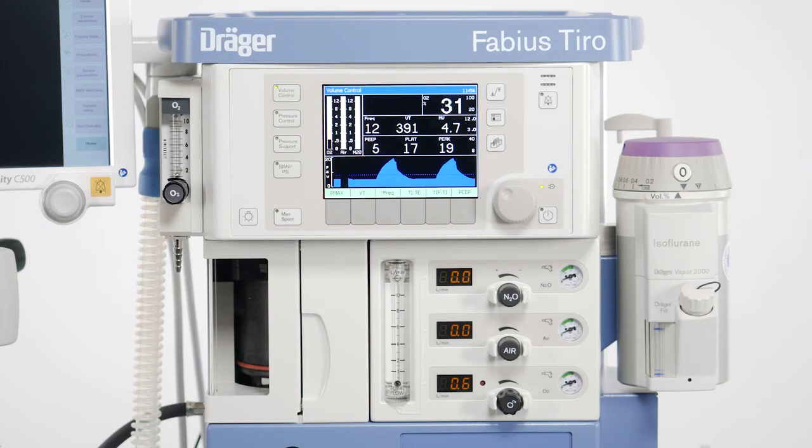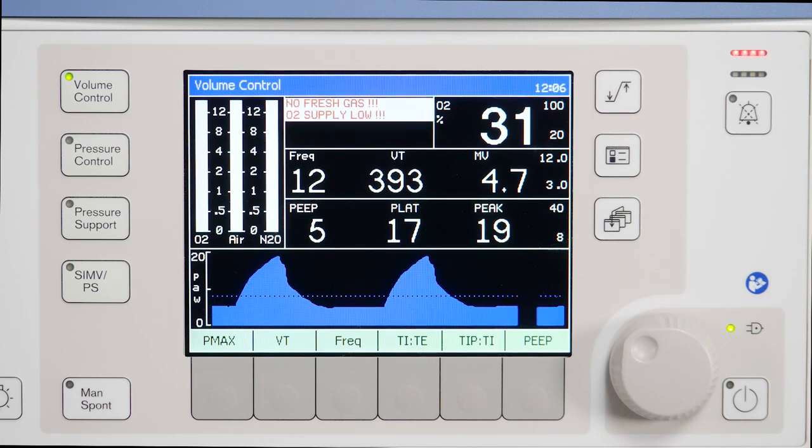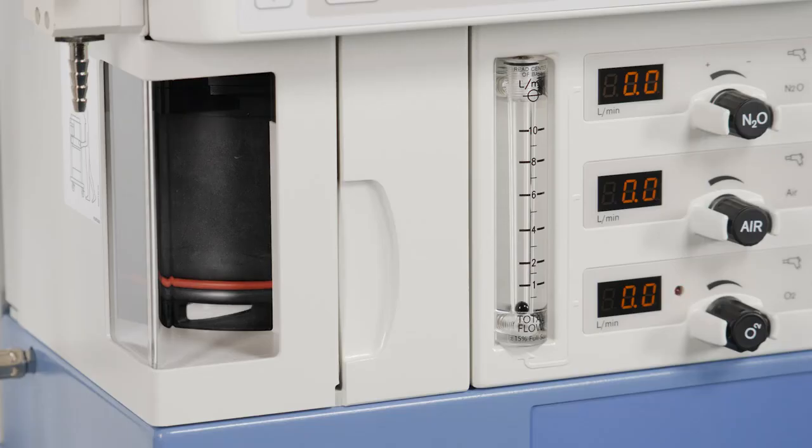Another advantage of the piston ventilator becomes apparent in the event of a central gas supply failure, when you have to quickly open the gas cylinders.